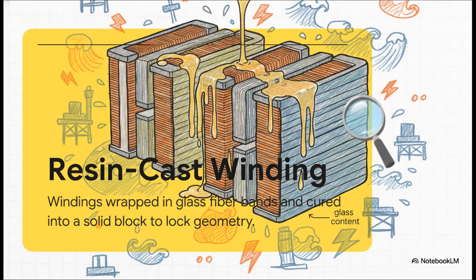Okay, let's move to the physical construction. You'll hear the term resin cast winding. But what does that actually mean? Well, it means the copper windings are tightly wrapped in resin-impregnated glass fiber bands, and then that whole structure is cured into a single, solid mechanical block. We're talking about an 80% glass content construction here. Curing it this way physically locks the coil geometry into place forever. It becomes this rigid, dense, immovable object.